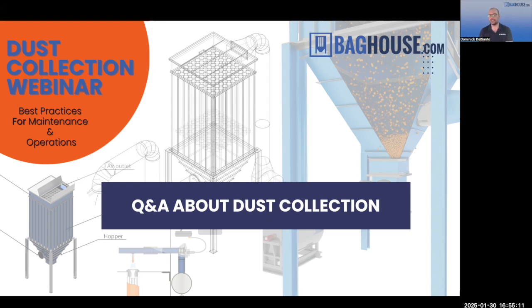In that special instance, it might be more economical and practical because it's a smaller collector. In a big collector, that would be extremely expensive. So the solution you outlined, where it's outside with the isolation valves and the normal explosion vents, makes more sense. But that's why we usually start at this, but then say let's talk about the process and figure out the best option for you.